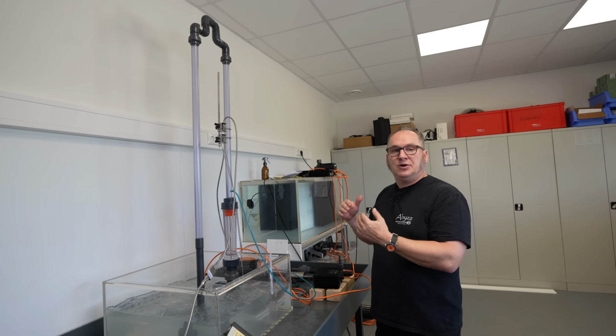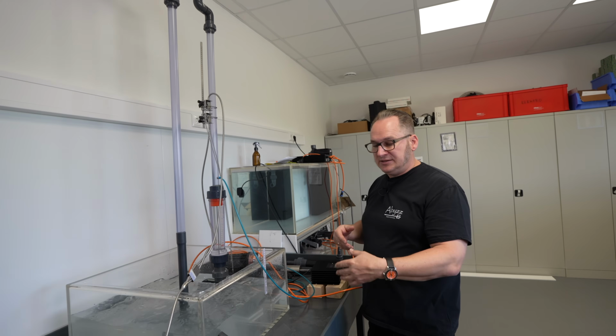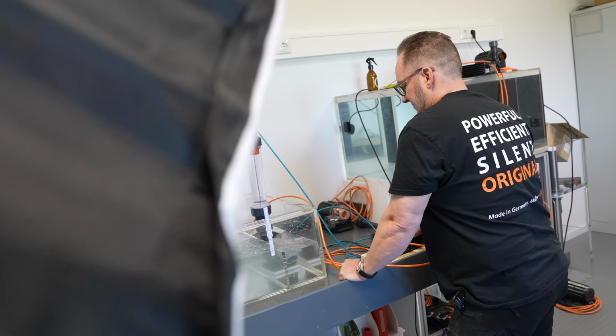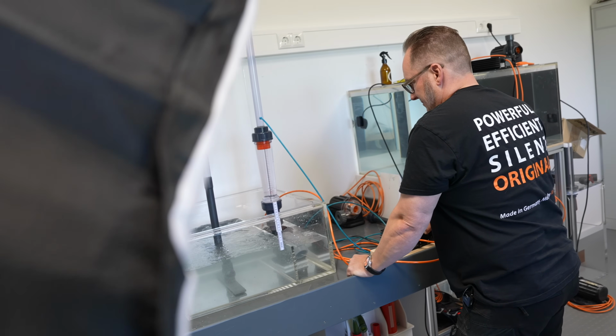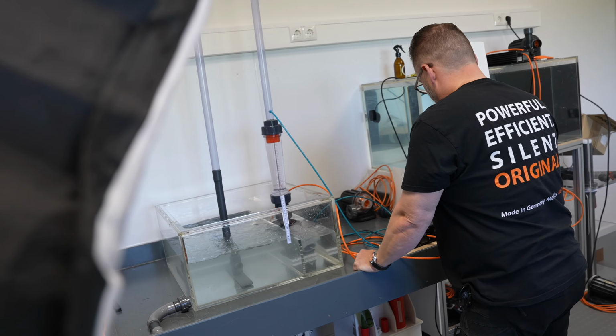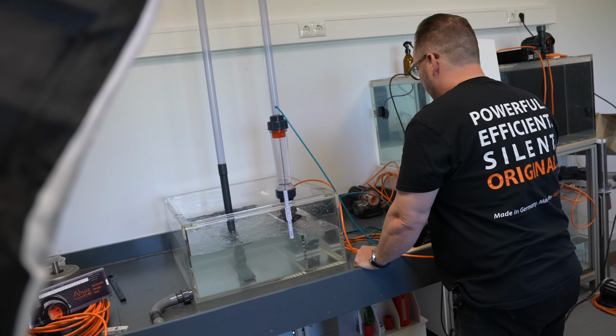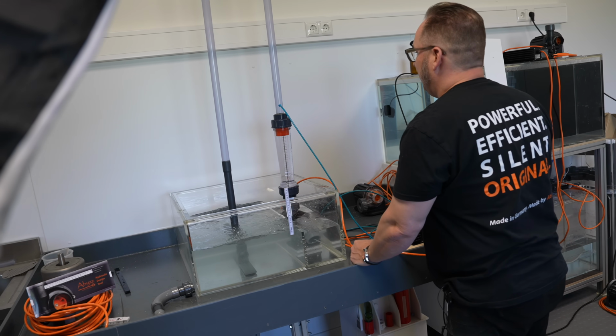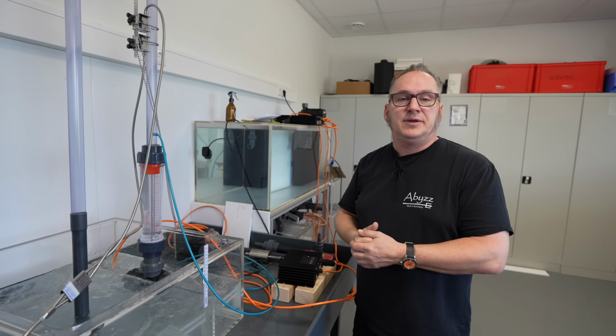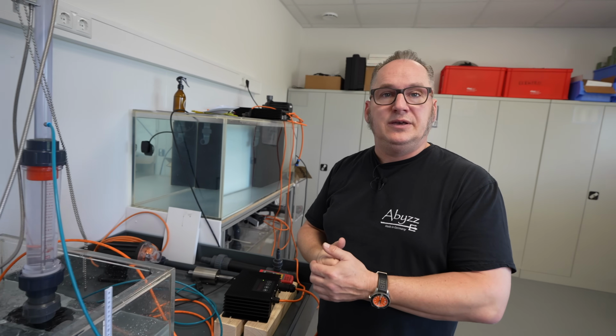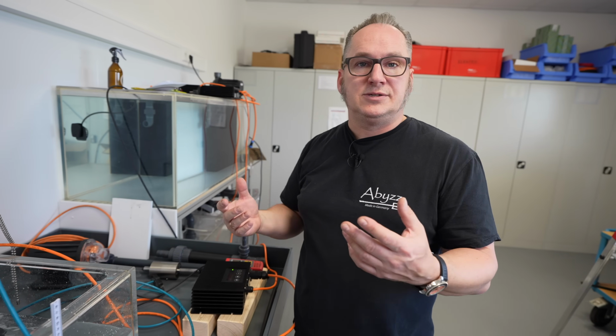That's why the pumps are so stable against head pressure. So they're still doing a good job, but you have roughly 12% less flow in the whole system at full speed, plus friction losses and noise. I mean, the noise is significantly higher in a plumbing like this than it would be if you had a larger plumbing and slower flow speeds.